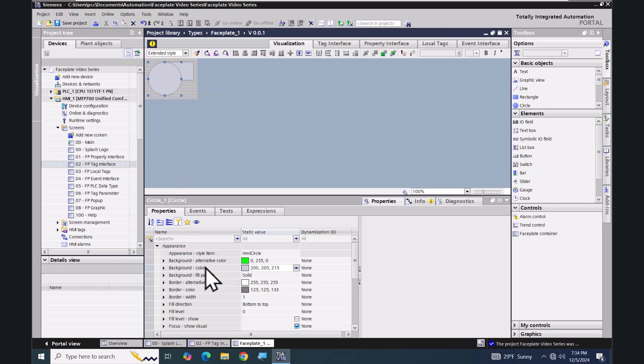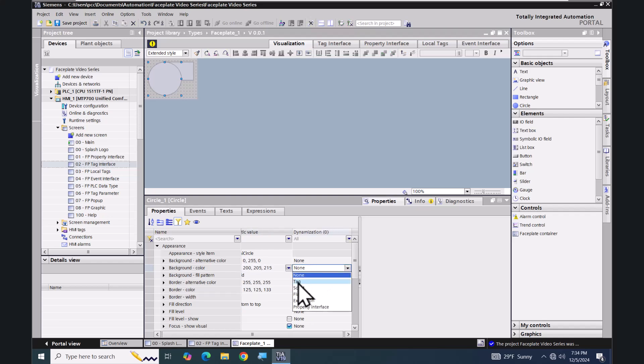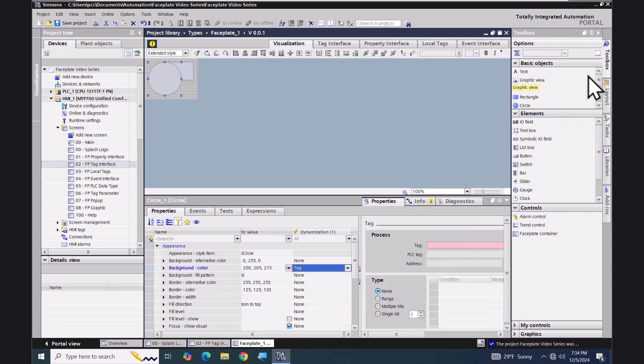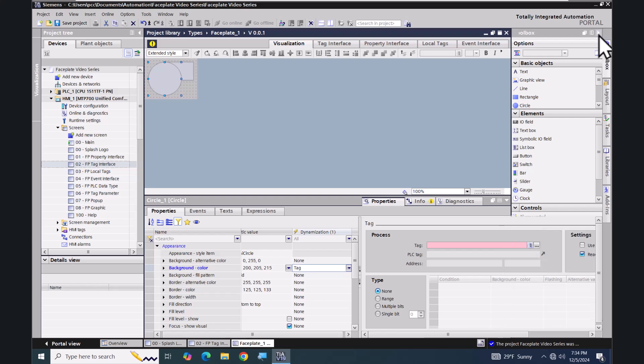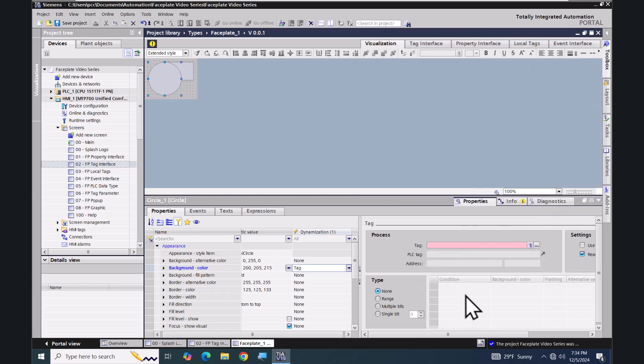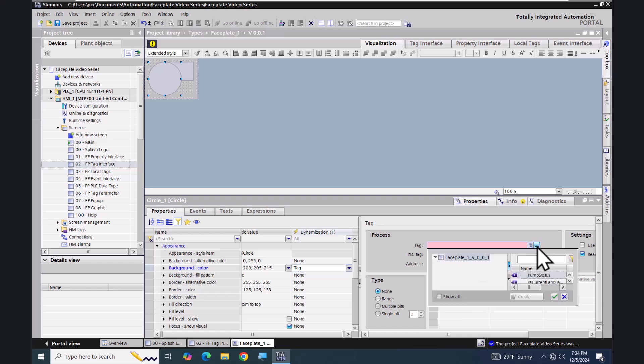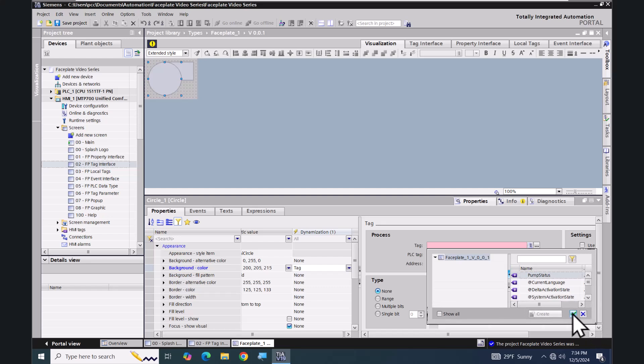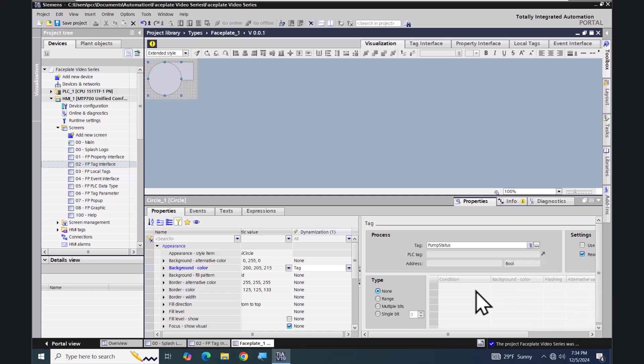I'm going to select the background color, double-click on 'None', and select 'Tag'. I'm going to minimize my toolbox area to have more room to enter the tag selection. I'll select the browse button — when browsing inside the faceplate, you can browse for the tags created on the tag interface tab. Here's the pump status tag, so I will select that.